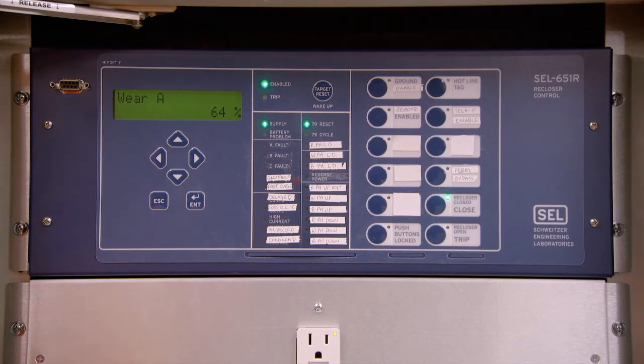If the amperage is increased, the calculation takes that into effect. So if you were to put 2,000 amps through this, it would take a percentage of the amperage that went through on that operation, which in turn would increase the wear monitor. There is a mathematical equation that is set into the actual control, so it knows the actual duty of that contact based on the magnitude of the fault that was applied. So if you had all minimum trips that were just at the threshold, this unit will perform up to 10,000 operations. Press Enter to escape.